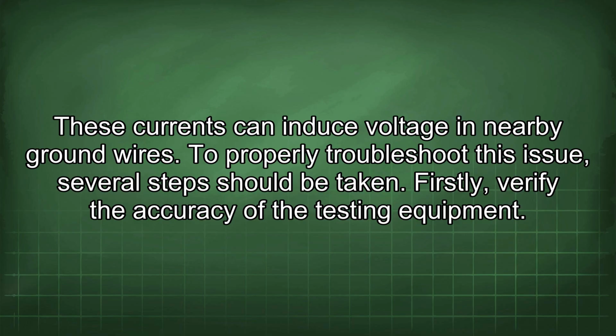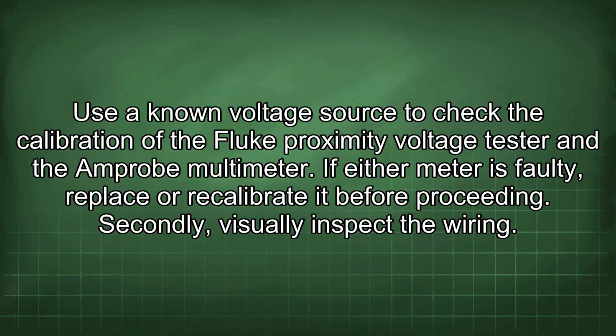To properly troubleshoot this issue, several steps should be taken. Firstly, verify the accuracy of the testing equipment. Use a known voltage source to check the calibration of the Fluke proximity voltage tester and the Amprobe multimeter. If either meter is faulty, replace or recalibrate it before proceeding. Secondly, visually inspect the wiring.